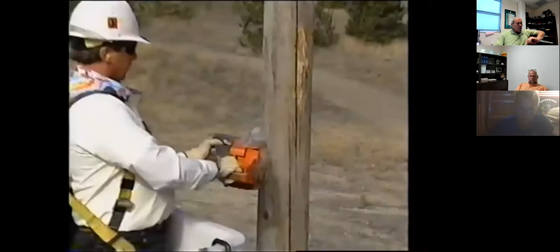There are two recognized methods of removing the top of the pole. The first is called chunking, when the top of the pole is removed in several sections, such as these. For safety reasons, chunking is the preferred method, allowing the lineman easier control of the smaller pieces. This may take longer, but it's well worth the extra effort.